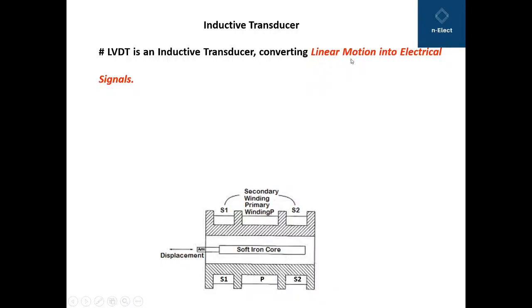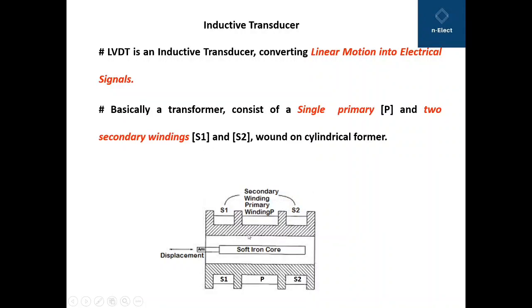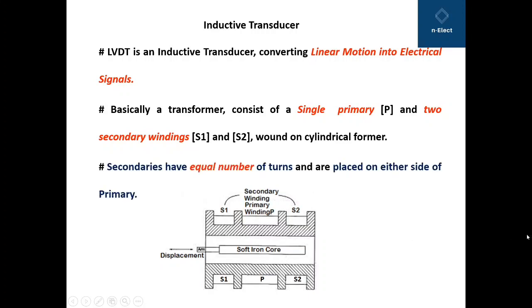LVDT basically converts the linear motion of the core into an electrical signal, that is, into a differential output voltage. It is essentially a transformer consisting of one primary winding and two secondary windings S1 and S2, which are wound on a cylindrical former. The secondaries have equal number of turns and are placed on either side of the primary.